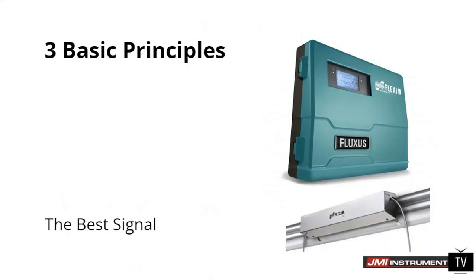Reflections, and we talked about that a little bit, from flanges. 3 to 7 diameters is where you don't want to install from a flange. Obviously the pipe wall: in order for us to get a good measurement, we have to have good contact, not only with the transducer, but with the dampening material that we're putting on the pipe. So flaky paint, pitting, things like that, we try to smooth out on the pipe. It can be painted, but it needs to be smooth.